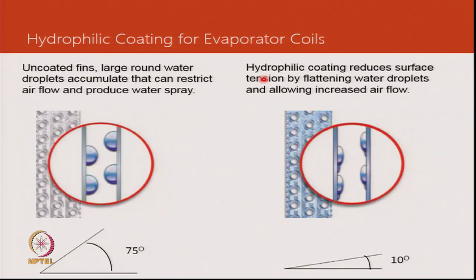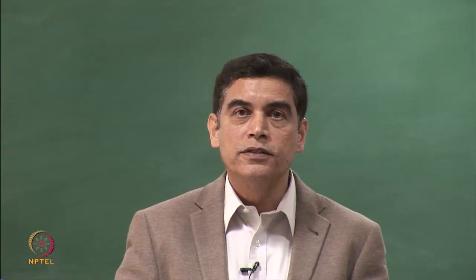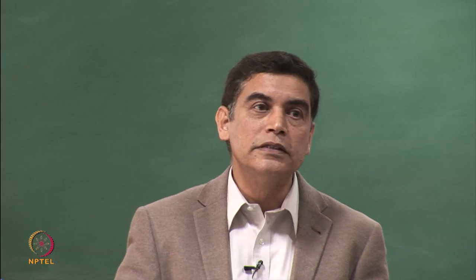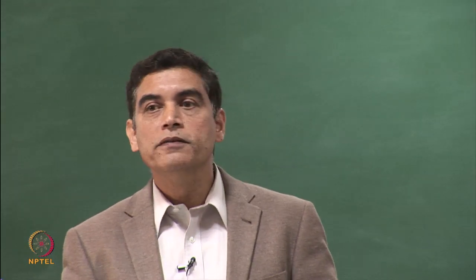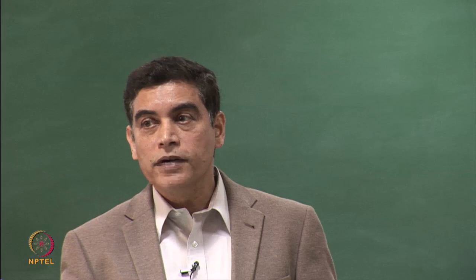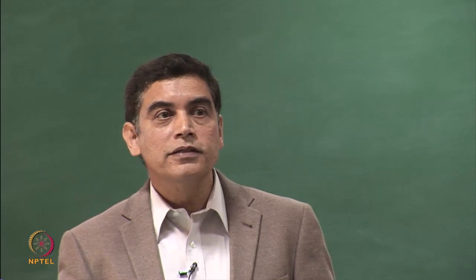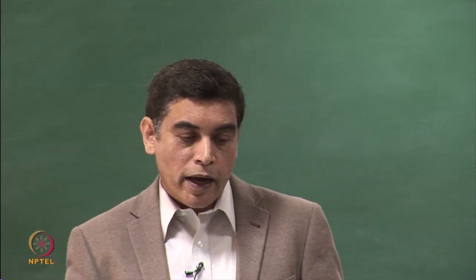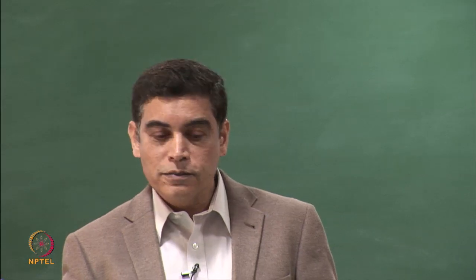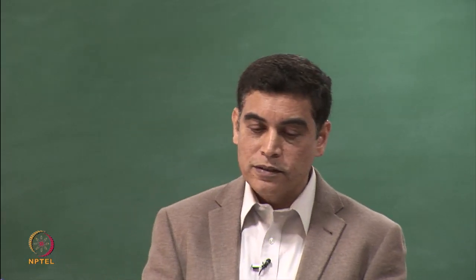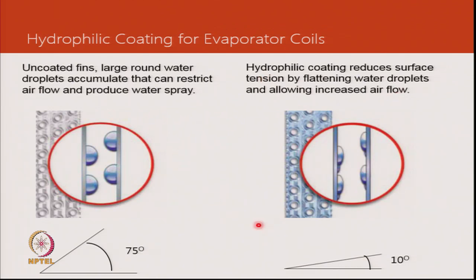One is to enhance the life, which it could withstand a salt spray test of say 500 hours, and it also changes the characteristics of the surface. So, the wettability of the fin surface changes, and that has two benefits. One is the condensate drains faster, the water film thickness on the fin is reduced, and carryover of droplets into the supply air is reduced. So, these are the benefits.